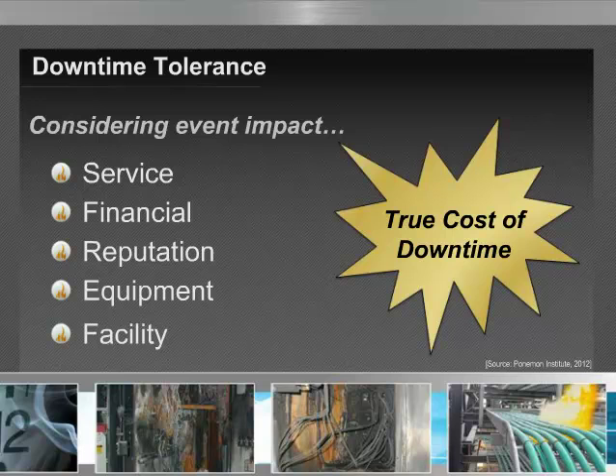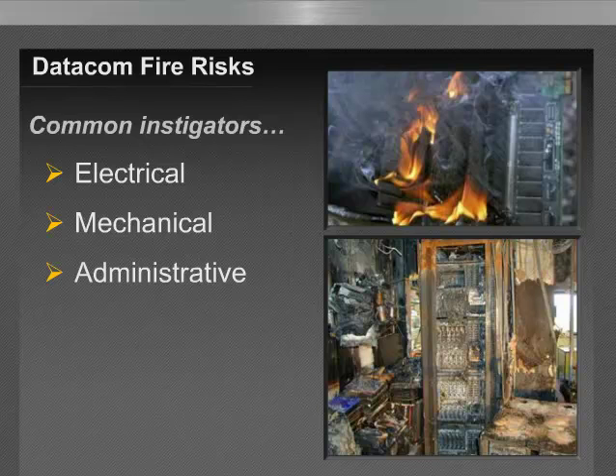So given that the consequences can be extreme, the importance of protection systems continues to grow in datacom facilities. And with that, we look at the various fire risks. The most common instigator of fire events in datacom facilities is building systems. This includes, but is not limited to, electrical systems, which might include power distribution systems, shorts, overloading, component degradation, or other electrical system malfunction. You can also look at overheating of cabling components and equipment resulting in combustion of polymers, which, when released into the environment, release toxic and corrosive gases that over time may damage electronic devices.